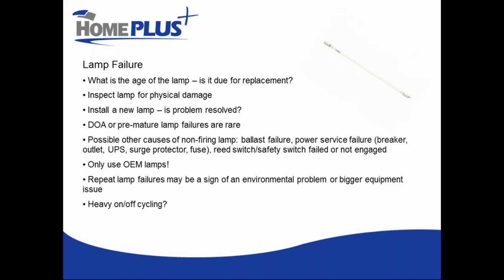You can inspect the lamp for damage. Often when there is a lamp failure, just like a fluorescent tube, you'll see blackening at the ends of the UV lamp that can be indicative of a problem. You could see a broken filament in it. There may be some obvious signs of damage. Inspecting the lamp is something you can do very, very quickly.